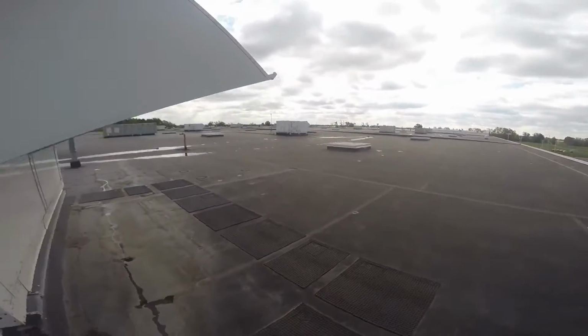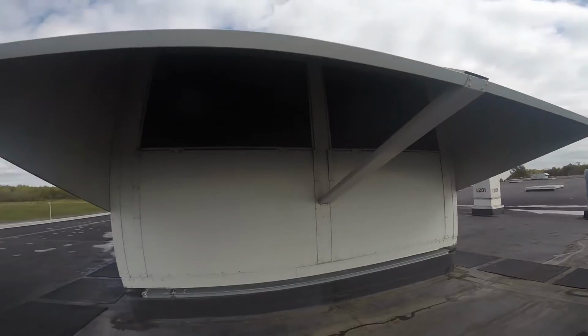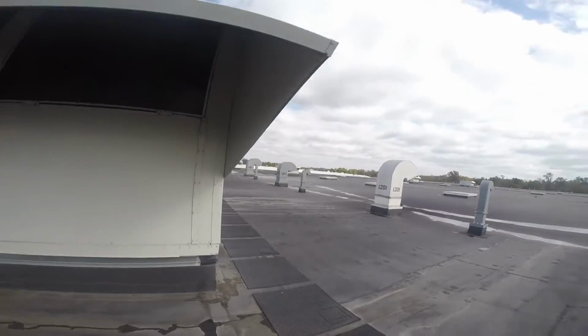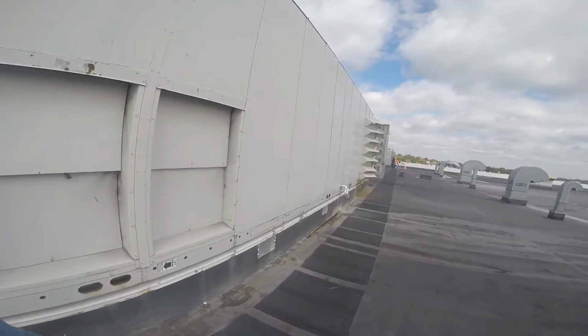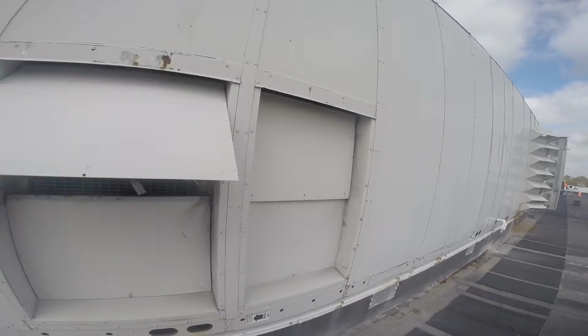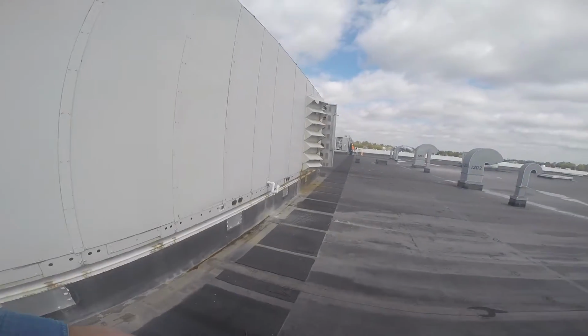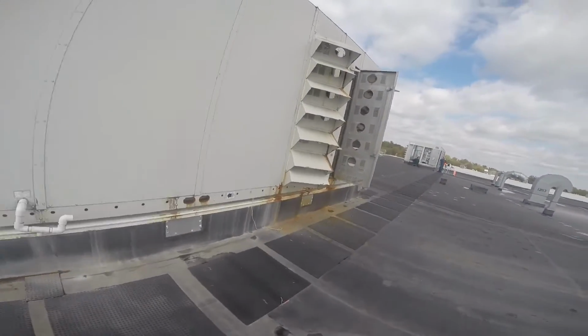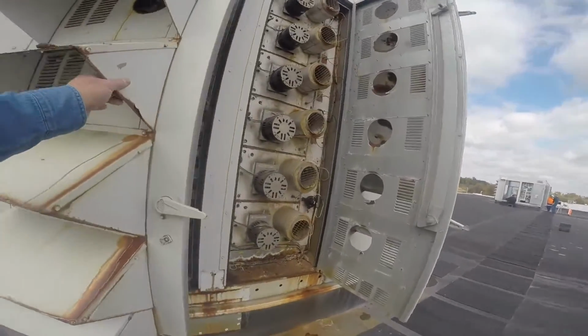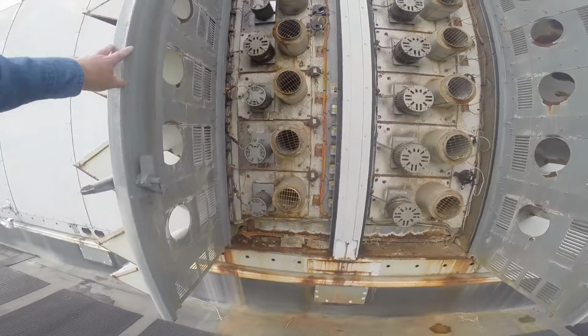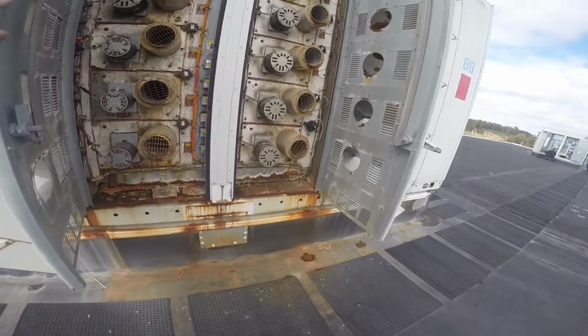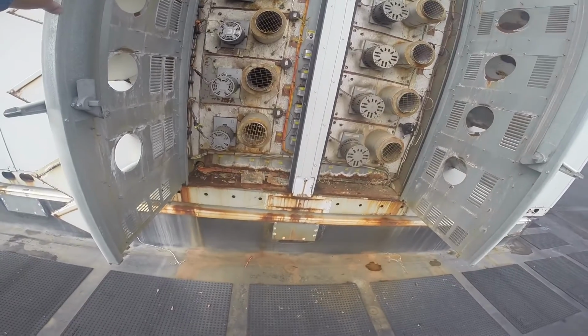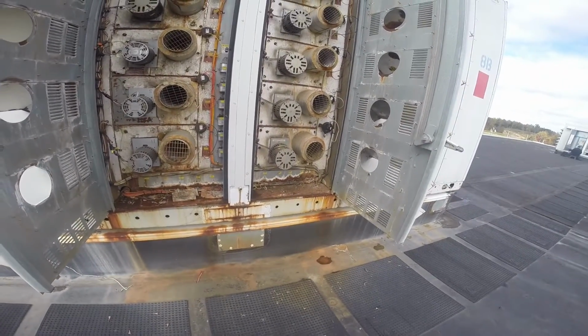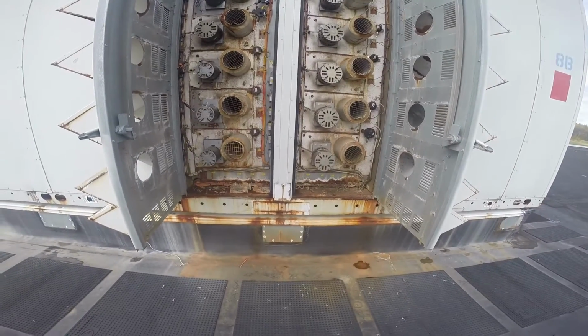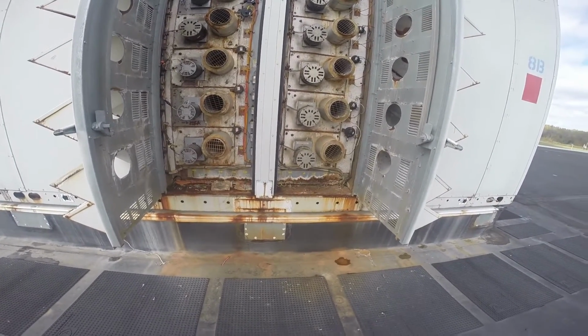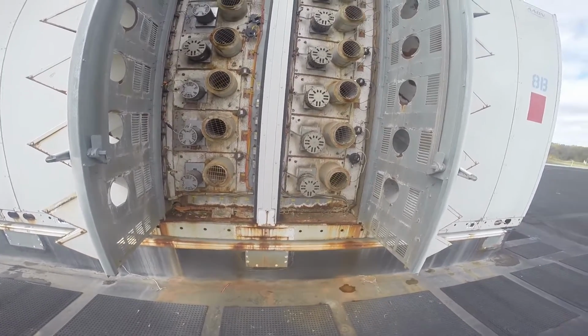We're going around the unit here. All relief dampers are working. This would be the other end of your heat exchanger where your induced draft motors are. You can see down at the bottom there where that's all rusted. Probably need to replace that with some stainless or something. That's probably going to continue to be somewhat wet down there, so we should put some kind of stainless or something down there to roll the water out on the roof instead of in the unit.